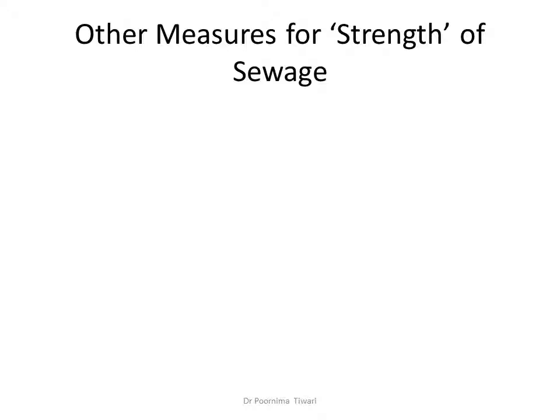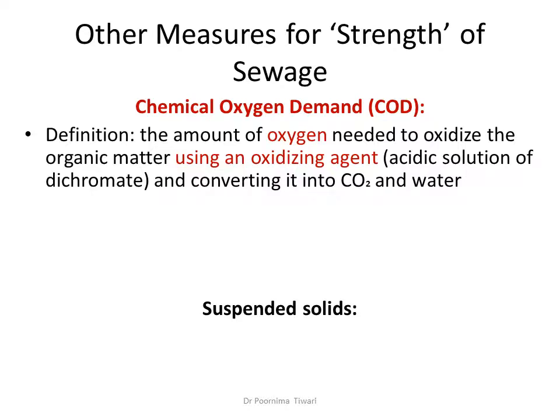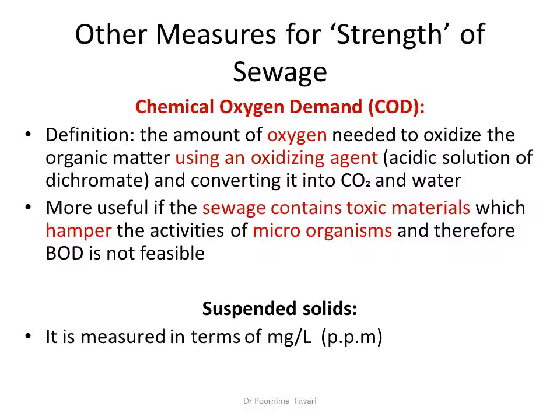Other measures for measuring the strength of sewage include chemical oxygen demand, or COD, and amount of suspended solids. COD is defined as the amount of oxygen required to oxidize the organic matter using an oxidizing agent, for example an acidic solution of dichromate, oxidizing the organic matter into carbon dioxide and water. COD is used where BOD is not applicable due to presence of toxic materials which interfere with the activities of microorganisms. Suspended solids are measured in terms of mg per litre or PPM (parts per million).